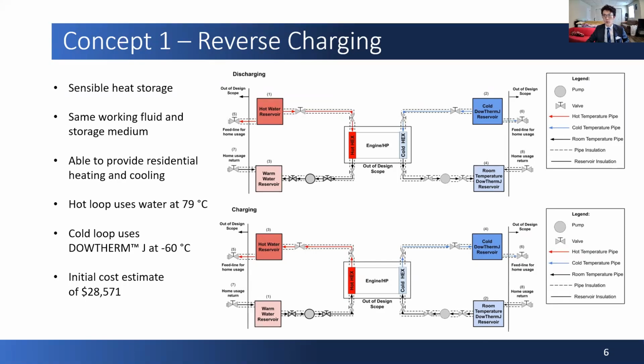Our first concept, reverse charging, utilizes sensible heat storage, with approximate dimensions being 4.9 meters by 4 meters by 1.7 meters. The system uses water for the hot reservoir, heated from 58 to 80 degrees Celsius, and uses Dowtherm J for the cold reservoir, cooled from 21 degrees to negative 60 degrees Celsius. This system is capable of providing heating and cooling to a home as well.